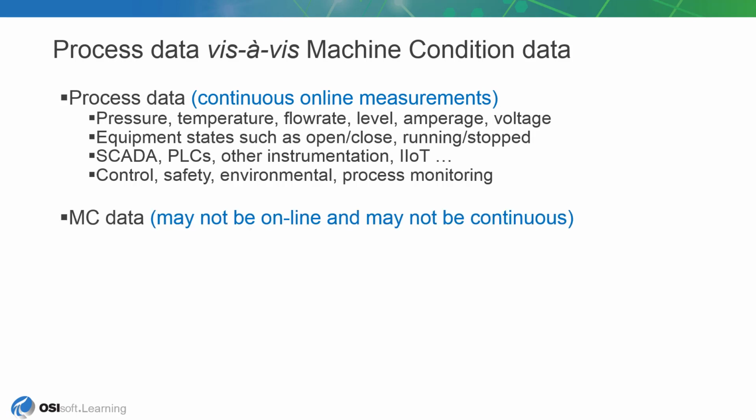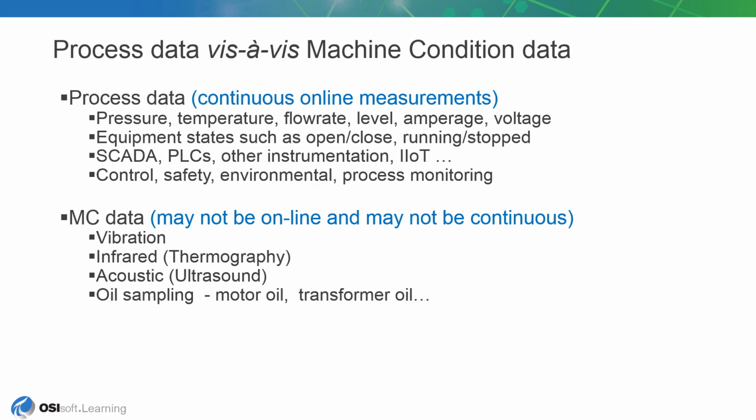Machine condition data usually comes into PI less often, and often they are in their own databases as part of a separate system. And the data is different. Vibration, infrared from the thermal guns, motor hotspot, junction boxes, oil analyses, particle and metal content, motor current, and so on.